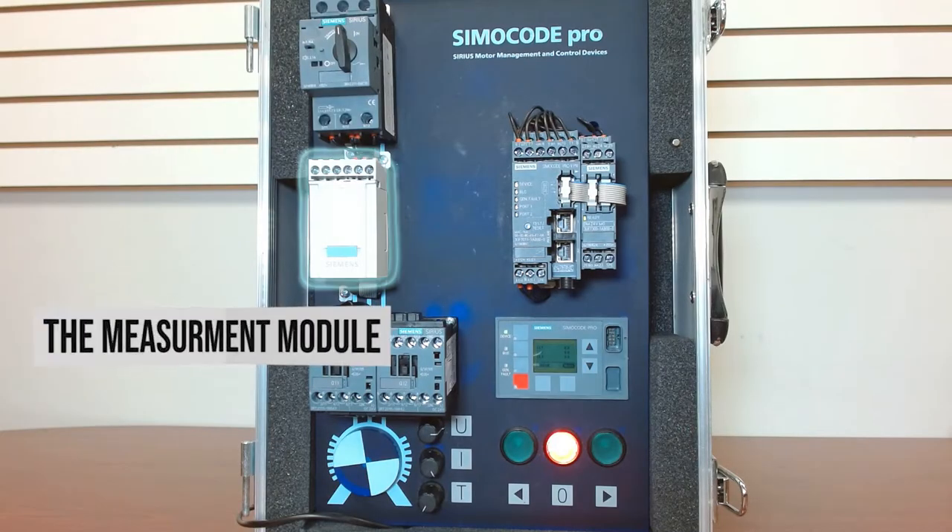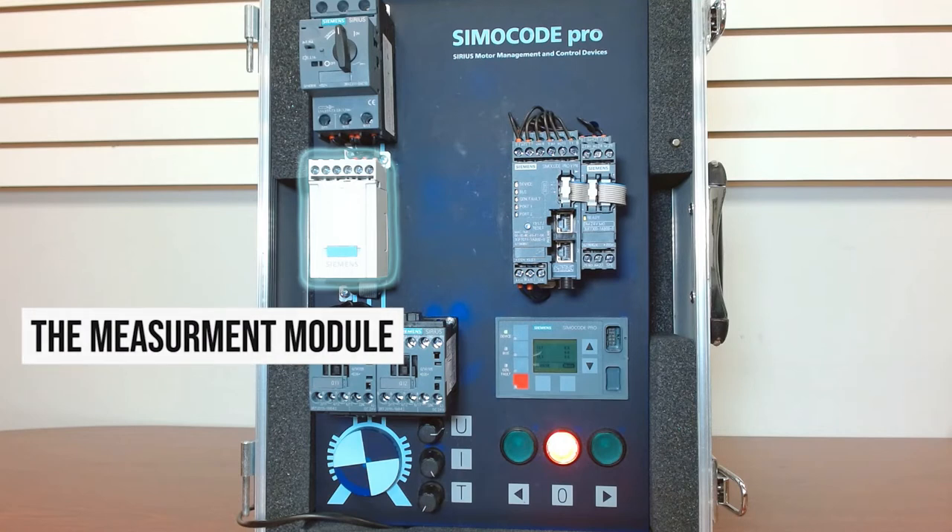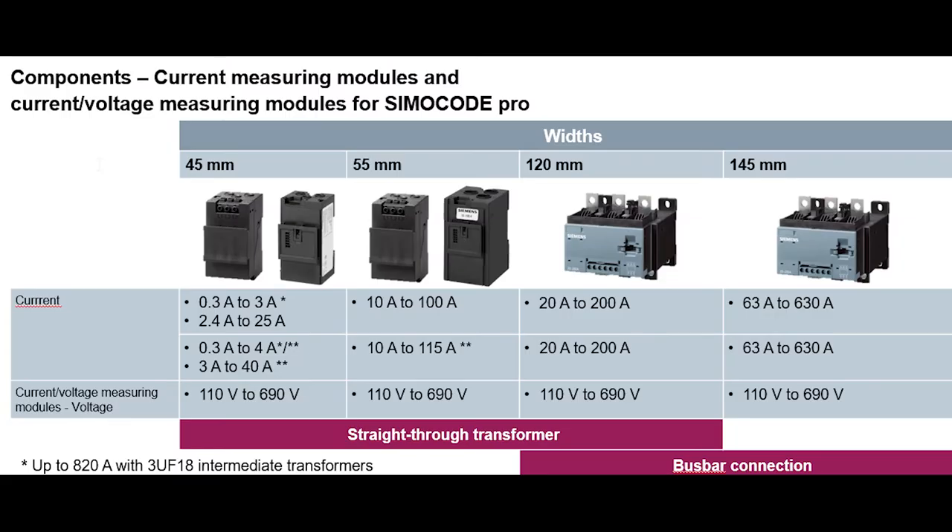So what are the different measuring modules that the SIMOCODE pro offers? For our demo here we have a current measuring module installed — you can see that highlighted right there. For the 45 millimeter options, the legacy Siemens units offer 0.3 to 3 amps or 2.4 to 25 amps. For the current offering, you have 0.3 to 4 amps or 3 amps to 40 amps. So for that 45 millimeter, there's a lot of flexibility from basically 0.3 up to 40 amps depending on the module you select.